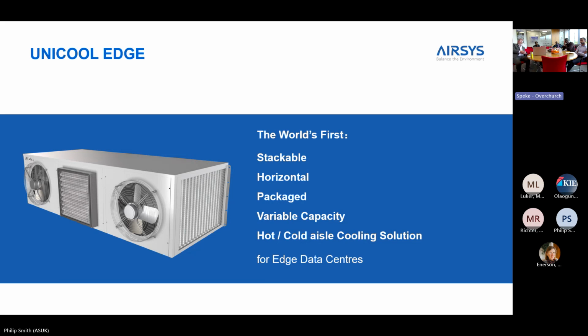We can then move on to techniques that combine fresh air and refrigerant as a means of cooling, and we make a variety of products. One of which is called the Unicool Edge, which is a new product. Do you remember the Eaton Williams BTX units? You had fresh air and DX combined in one box. You put it against a wall, and it would bring fresh air in, and if the fresh air was hot, it would use the DX instead. That's mature technology. We still make those units. They're on a couple of slides later. They work very well.